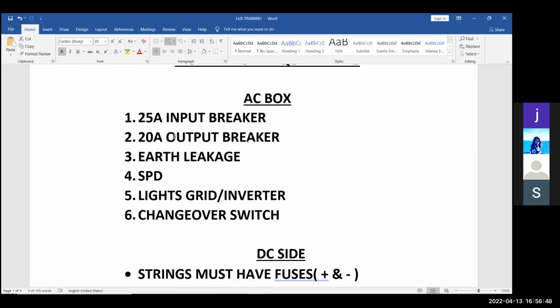Your changeover switch is not that expensive, but if something goes wrong in your systems, the client has the capability just to switch over the house to Eskom. We have systems where the settings are not done right. The client can't get hold of the installer and they are sitting without power in their house. Please put in a changeover switch for your clients to have the ability to change over from the inverters to Eskom to provide the house with loads.